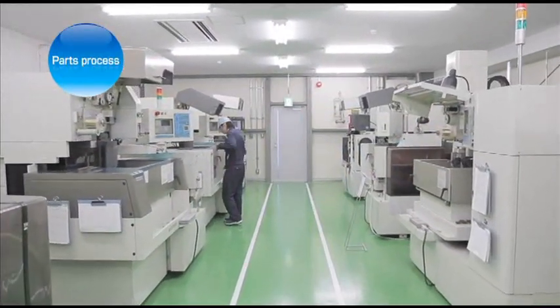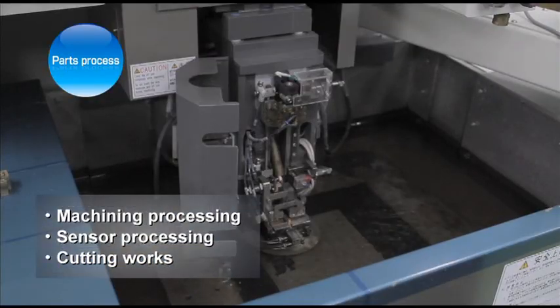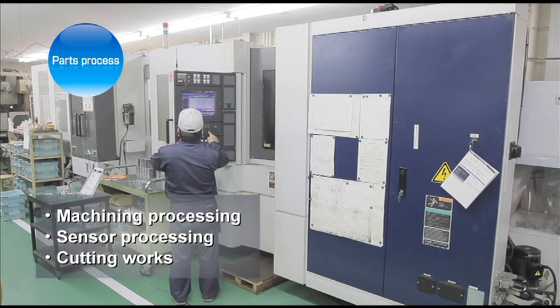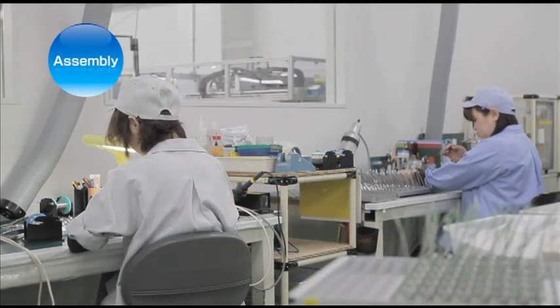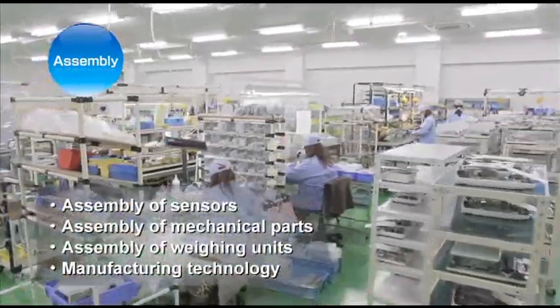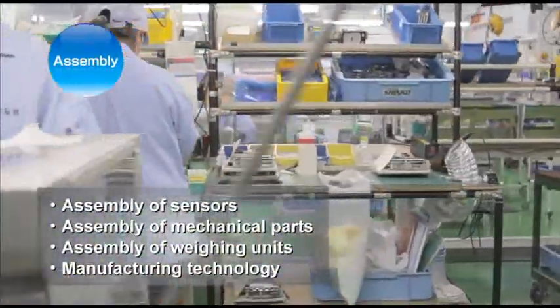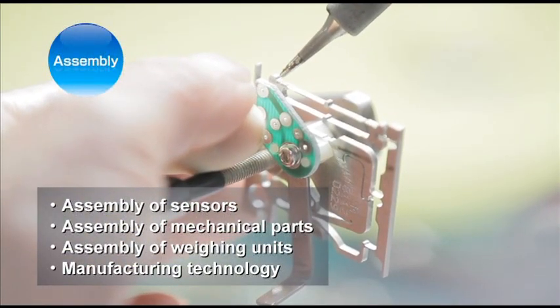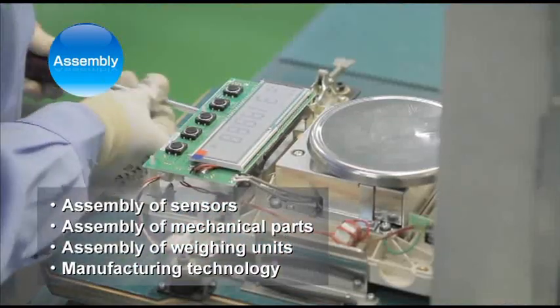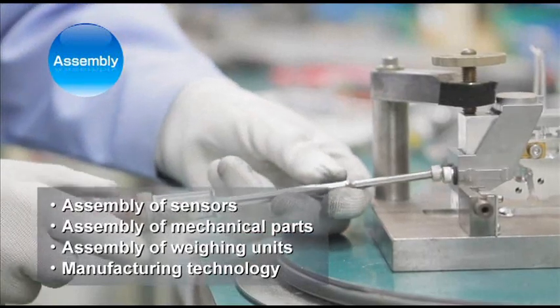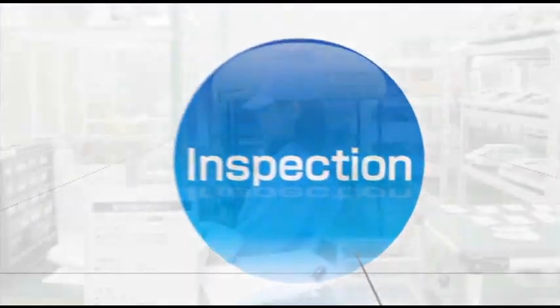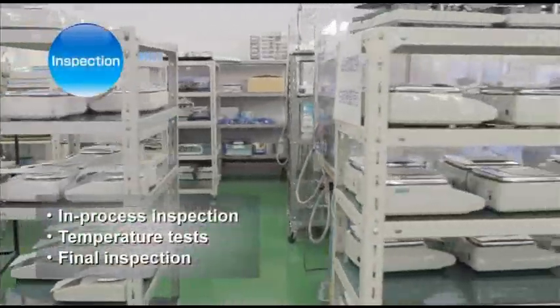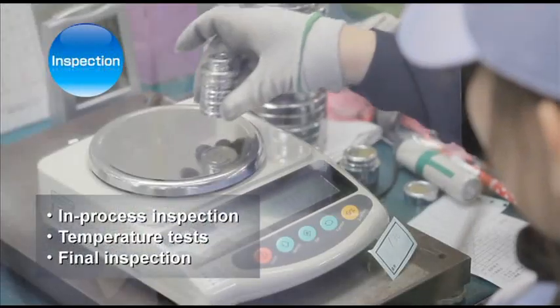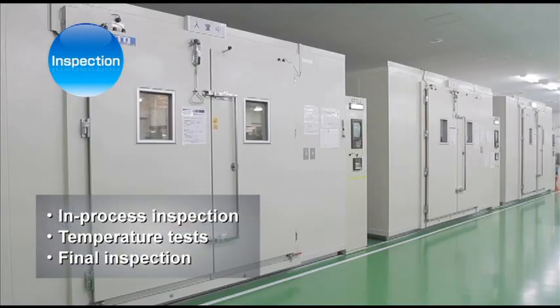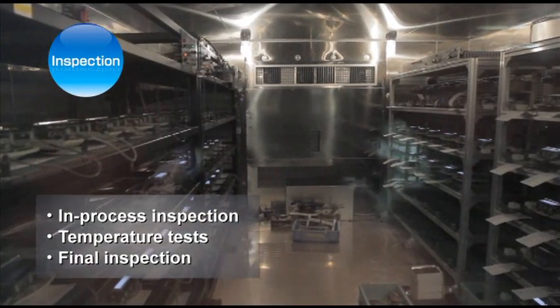In this parts processing line, the tuning fork sensor, which is essential to our scales, is machined and cut using high accuracy processing technologies. In this line, the sensors, mechanical sections, and weighing sections are assembled. Experienced operators carefully assemble these precision parts manually. Assembled products are closely checked for any operational and technical problems. A temperature test is also conducted to guarantee product performance.